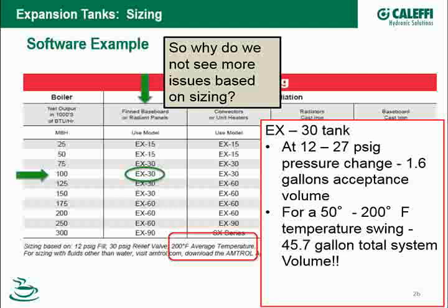If I'm putting this in a modern system, condensing boiler, low water content, maybe 15 to 20 gallons of total water in the system. This is why a lot of these expansion tanks, I'm saying I'm sizing for 27 psi. In reality, the high pressure, when the water reaches this high temperature, is topping out at maybe 17 or 18. It's because this chart is very conservative.